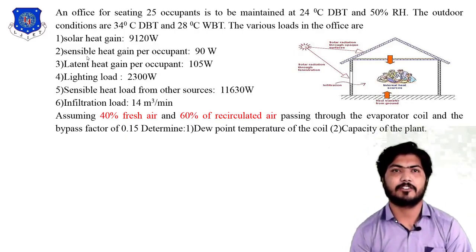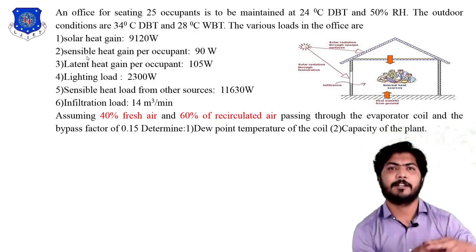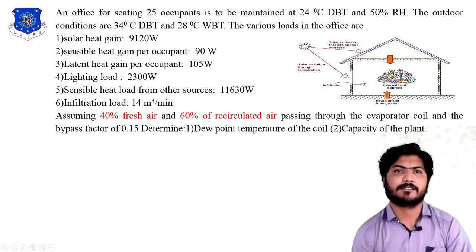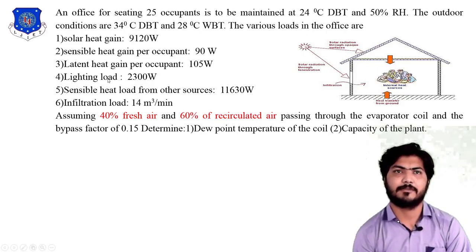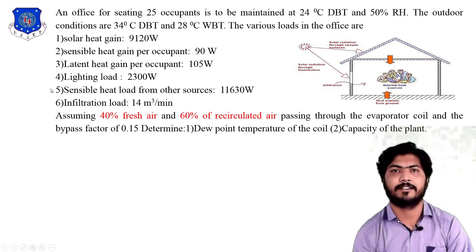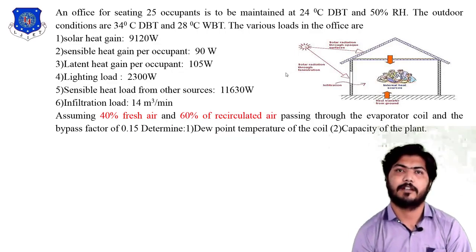First, we understand which load comes under sensible heat and which comes under latent heat, as already explained in the previous Load Analysis Lecture Part 1. Solar heat gain comes under sensible heat, sensible heat gain also comes under sensible heat, latent heat load comes under latent heat, lighting load comes under sensible heat gain. Infiltration load of 14 cubic meters per minute is the air volume flow rate which comes inside the room through cracks, windows, or lower openings.